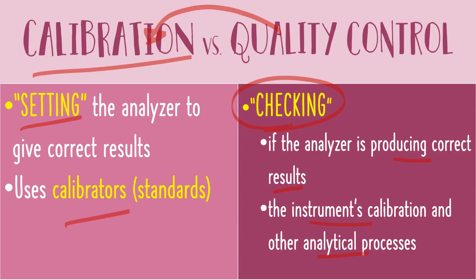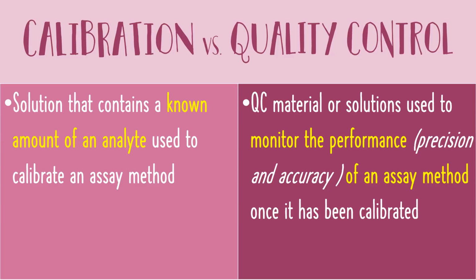Because if in case that there is a problem in calibration, then quality control results will usually be fluctuating, and that is actually indicating error, so indicating that there is a problem in your calibrating procedure. So in order to perform calibration and quality control, we are going to make use of reagents. So for calibration, we are going to make use of a solution that contains a known amount of analyte that is used to calibrate or to set an assay method. Meanwhile, quality control solutions are used to monitor the performance of an assay method once it has been calibrated.